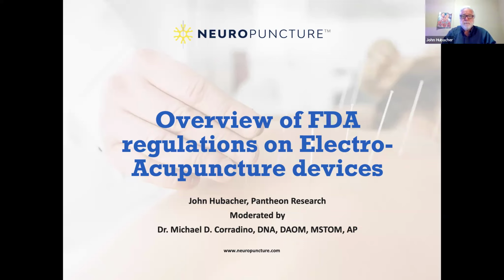And there's a list of all devices that have been registered through the FDA 510K process for BWK, or specifically electroacupuncture. Now, it's illegal to have a device that you make false claims about; describing it otherwise is a misrepresentation, they call it, of its registered applications. An electroacupuncture device registered with BWK and with your 510K, you are allowed to use it for electroacupuncture according to how the states regulate your scope of practice. You can't use a TENS device, according to law, as an electroacupuncture device. And in fact, it may not be safe because they're quite different. Definitely. It's important that that distinction is known for people.